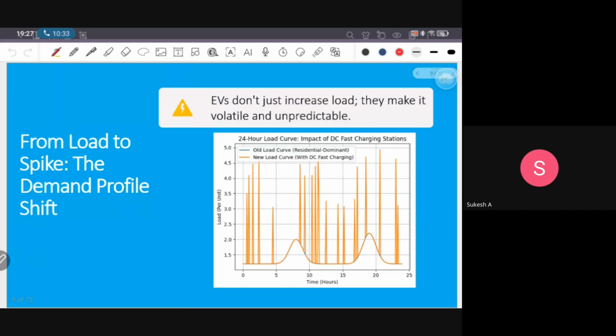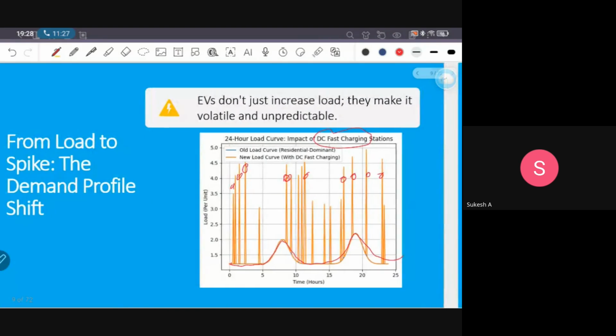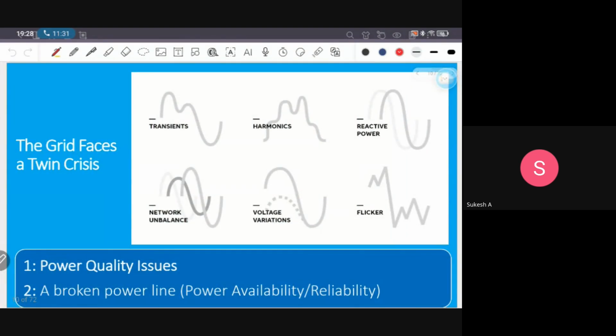And we can see here a 24-hour curve of the impact of DC fast charging, or DCFC. This is the normal curve. We can see the spikes in the load demand here. Irrespective of the ongoing or normal demand, these spikes appear in the load demand curve. But we cannot control this load demand, because these spikes are because of DC fast charging of electric vehicles. We cannot directly control this fast charging because it is the customer's need. The customer may need it at night, at midnight, in the morning, or at noon. So we don't have control over it. It is another main issue we are facing at the start of this EV system.